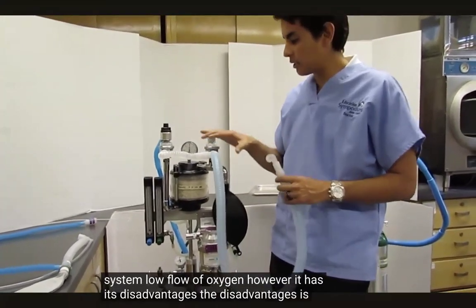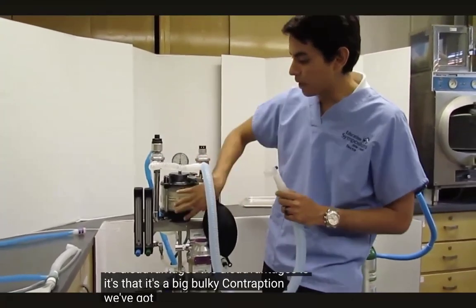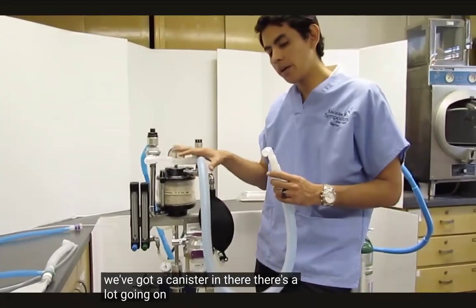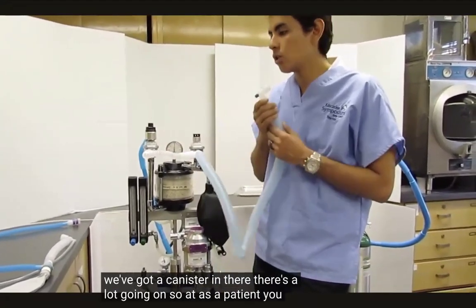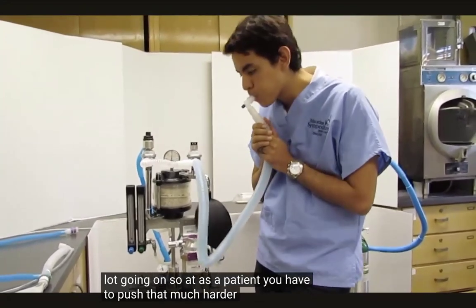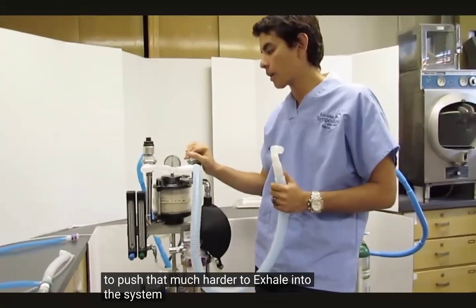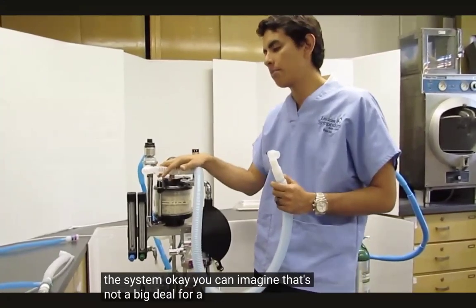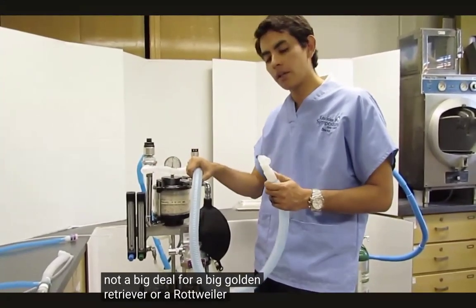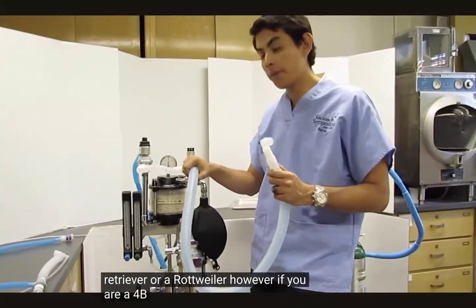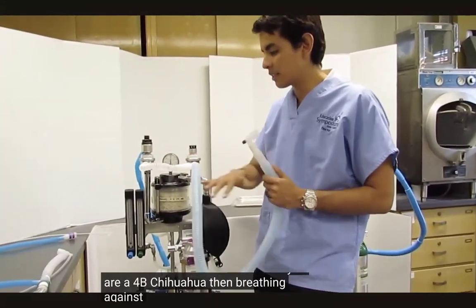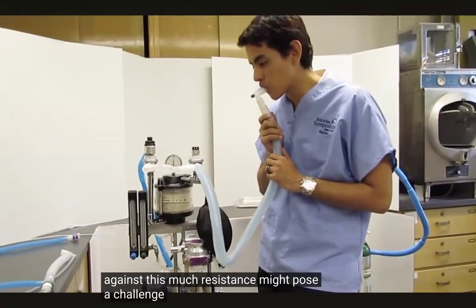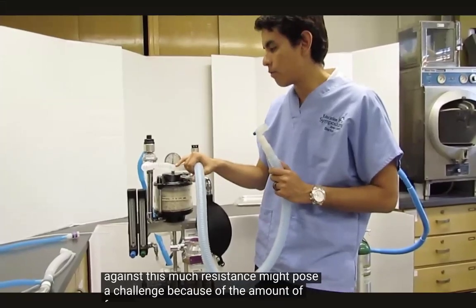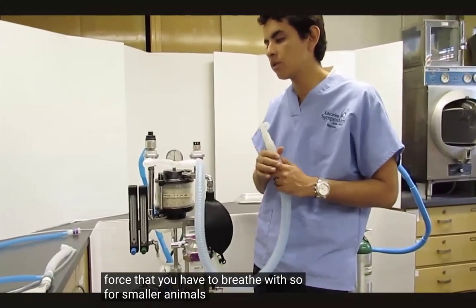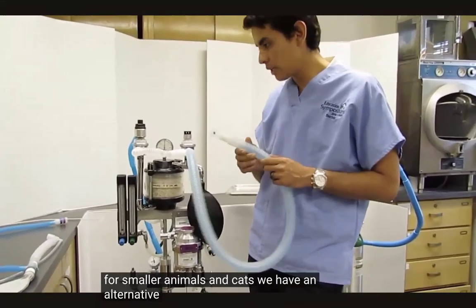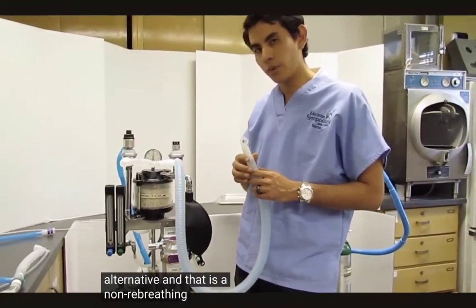The disadvantage is that it's a big bulky contraption. We've got a canister in there. There's a lot going on. So as a patient, you have to push that much harder to exhale into the system. You can imagine that's not a big deal for a big golden retriever or a Rottweiler. However, if you are a 4-pound Chihuahua, then breathing against this much resistance might pose a challenge because of the amount of force that you have to breathe with. So for smaller animals and cats, we have an alternative, and that is a non-rebreathing circuit.